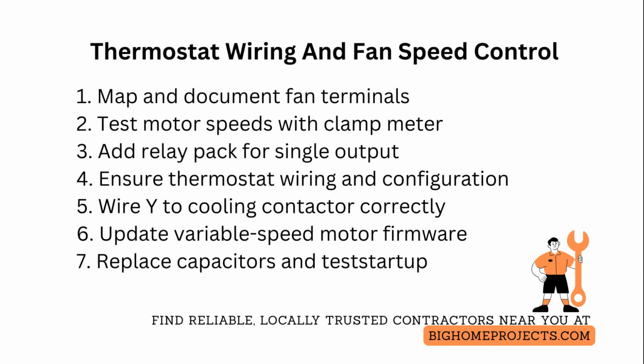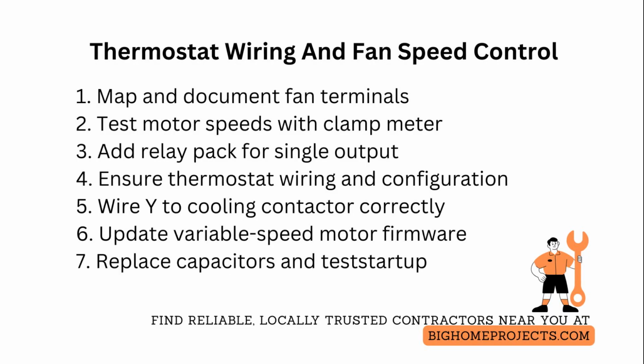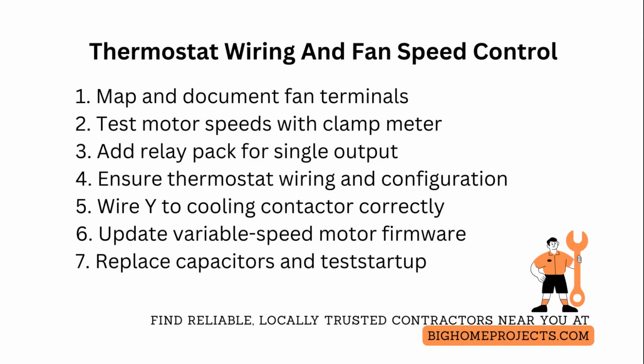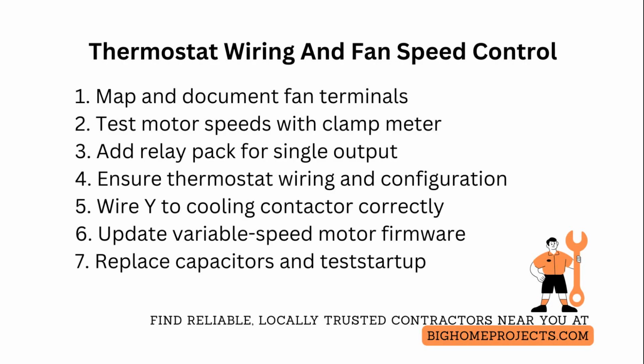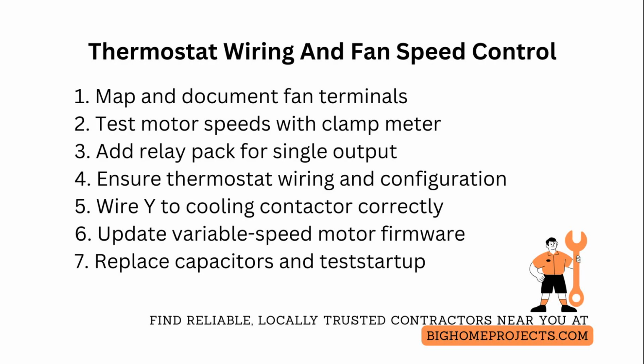If the control board only has a single variable output, install a 3-speed relay pack or a multi-tap transformer to provide discrete heat and cool taps. And set the fan control jumpers per the manufacturer to prevent overlapping contacts during mode transitions. When replacing thermostats, ensure the thermostat fan terminal is wired to G and that the thermostat is configured to use conventional heat-cool sequencing rather than zone or variable speed profiles.